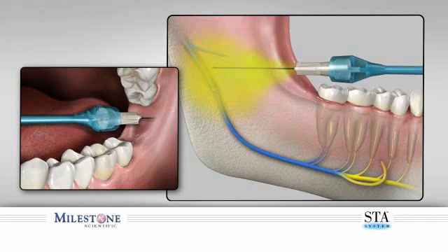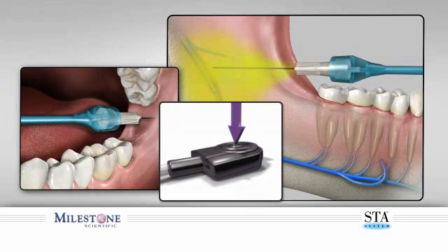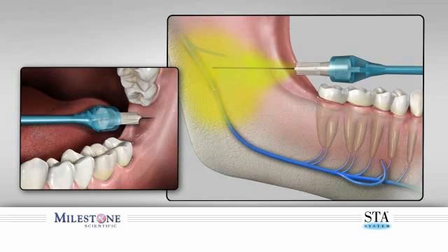Continue the injection by depressing the foot control pedal. It is recommended that the first quarter of the cartridge be dispensed using the control flow rate before transitioning to the faster rapid flow rate. The rapid flow rate is used during block injections only after your patient has acknowledged that they have achieved soft tissue anesthesia of the area being injected.